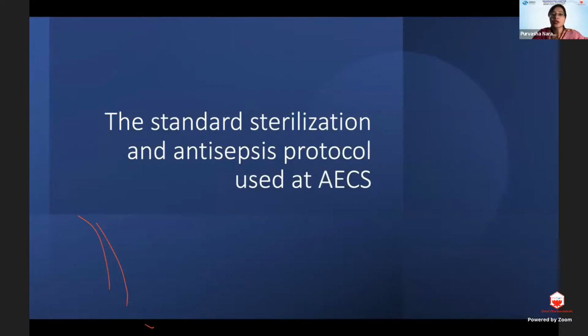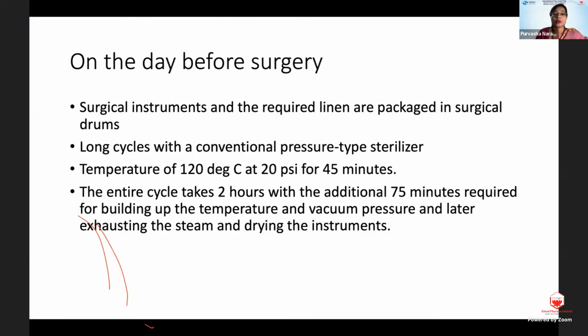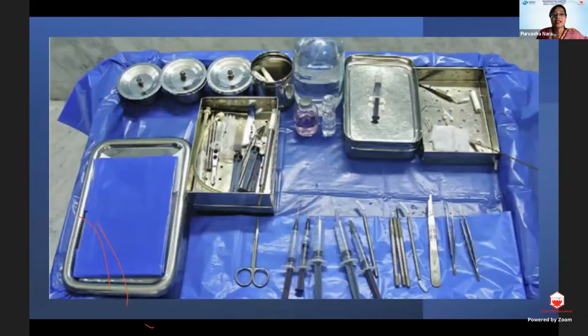So I am just trying to share a few sterilization protocols which are used at Aravind Eye Care System, because it is a very high volume, high cataract load system with a very minimal endophthalmitis rate. So I think that deserves an applause. On the day before surgery, they pass these instruments in a packed state in a long cycle of steam sterilization at a temperature of 120 degrees for 45 minutes. So basically it takes 2 hours, and an additional 75 minutes for the total cycle to take place. Whereas in between cases, they do the short cycle sterilization of 134 degrees for 17 minutes in total. So they have this kind of a procedure where they reuse multiple things, but because they have these stringent protocols, they are able to manage with a very low endophthalmitis rate.